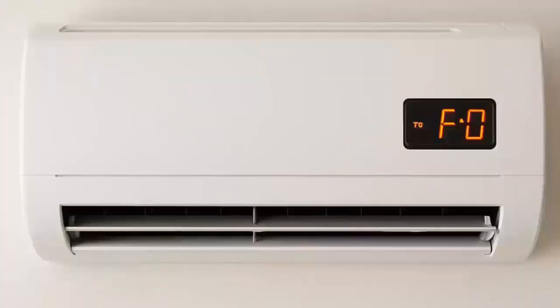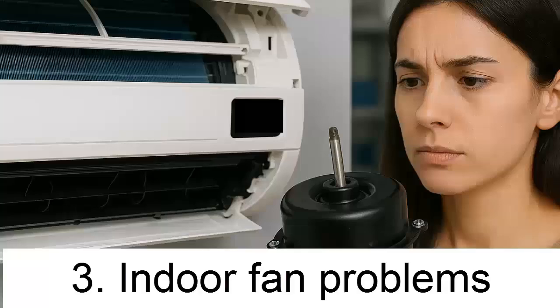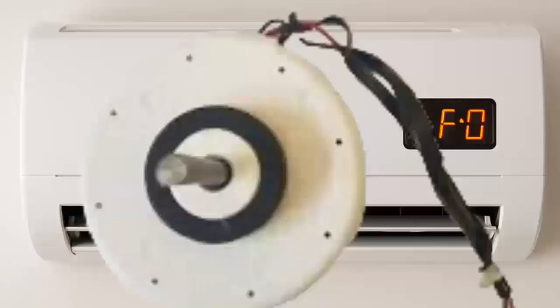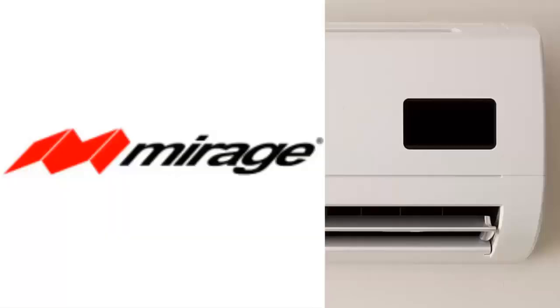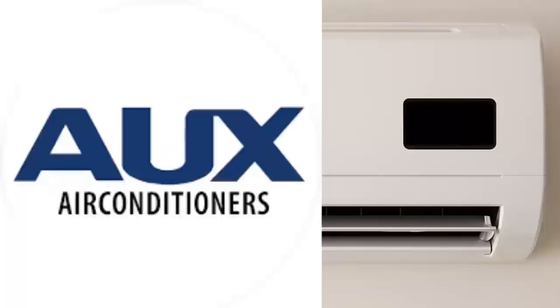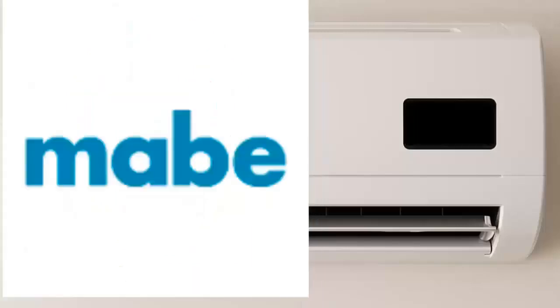Third category: indoor fan problems. The fan might spin slowly or not work at all. This meaning of the F0 error is less common and used by just a few brands or models. Mirage, Pioneer, AUX, Westmont, and some models from Mabe.